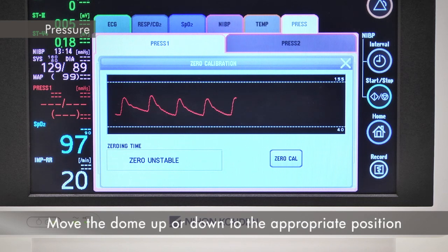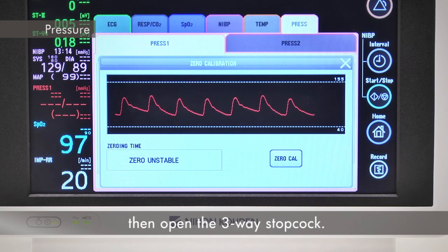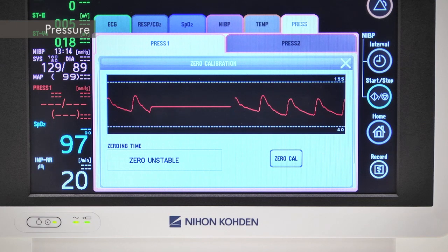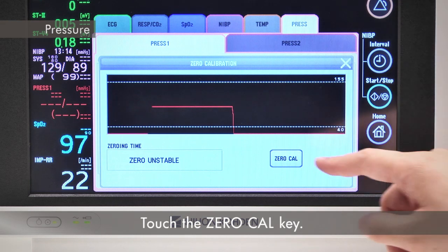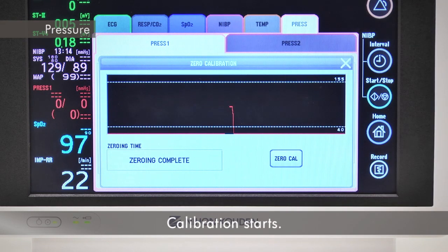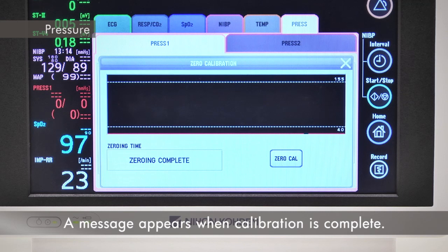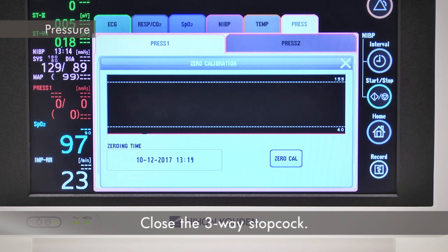Move the dome up or down to the appropriate position, then open the 3-way stopcock. Touch the 0 Cal key, and calibration starts. A message appears when calibration is complete. Close the 3-way stopcock.